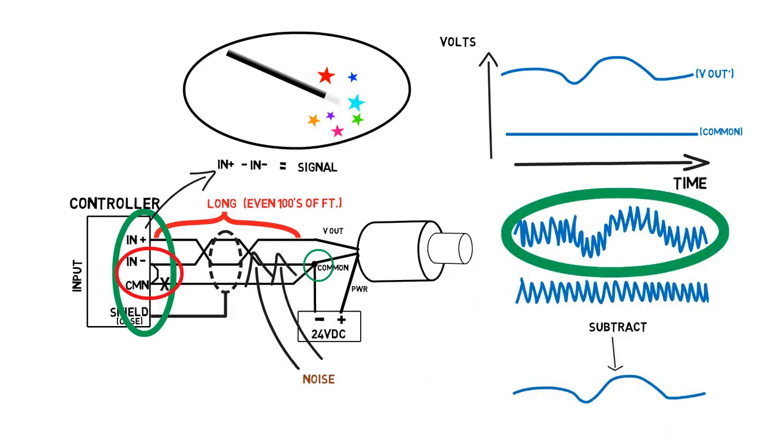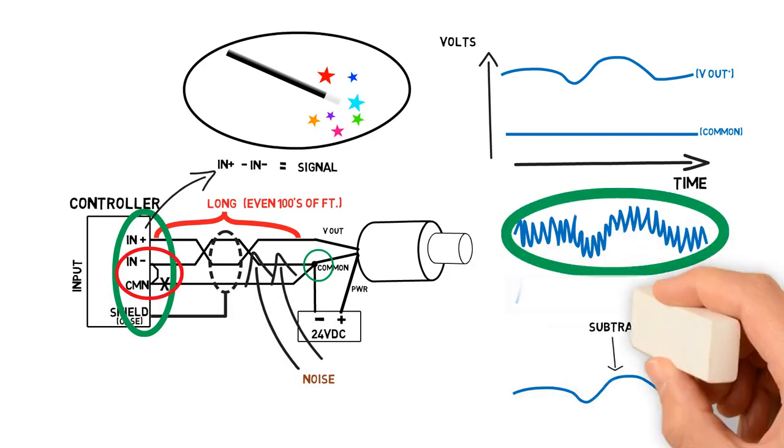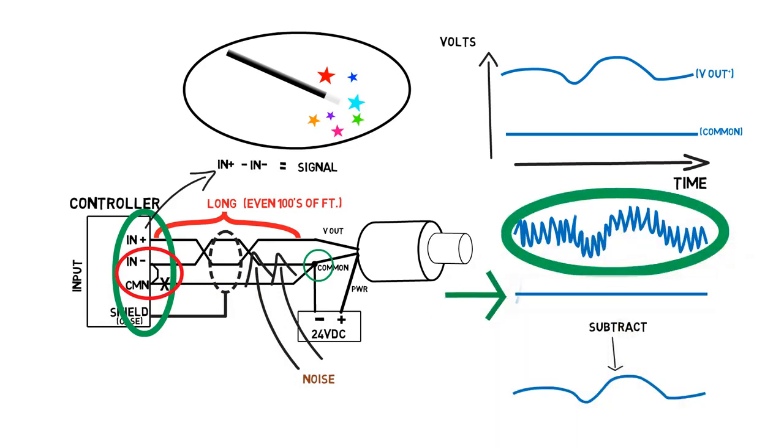The in plus pin will see the noise, but the in minus pin does not see any noise because that noise is shunted directly to common. Therefore, subtracting the signals cannot cancel the noise.